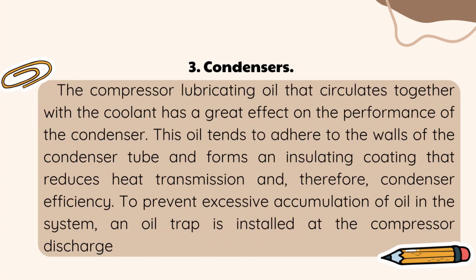3. Condensers. The compressor lubricating oil that circulates together with the coolant has a great effect on the performance of the condenser. This oil tends to adhere to the walls of the condenser tube and forms an insulating coating that reduces heat transmission and, therefore, condenser efficiency. To prevent excessive accumulation of oil in the system, an oil trap is installed at the compressor discharge.